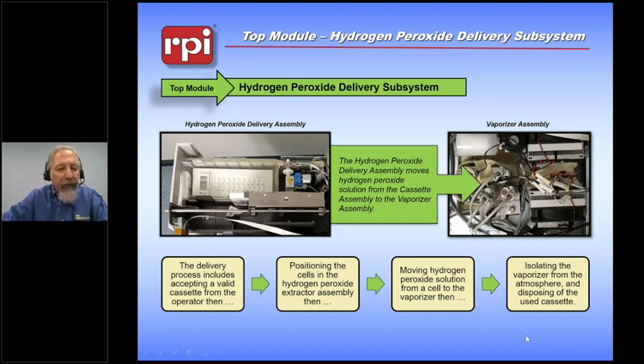This is the hydrogen peroxide delivery system. And basically what you have is a cartridge. There are 10 openings in the cartridge. Each run requires 2 of these slots to make up the complete hydrogen peroxide delivery. In the process of putting in a cassette, there is a barcode reader that reads the barcode on the cassette. That barcode contains the outdate for the cassette and information about that specific manufacturing process for that cassette. There is also one additional barcode on this tray assembly, and that's how the machine knows if the tray is filled, because the barcode reader, which is over here, and let me turn the laser pointer back on, the barcode reader over here can no longer see this barcode when the tray is full.